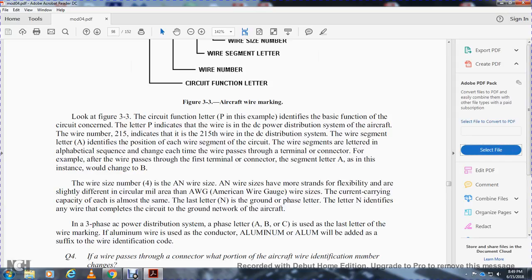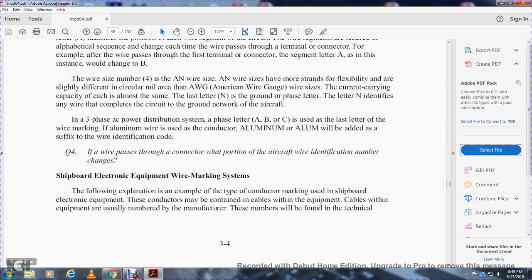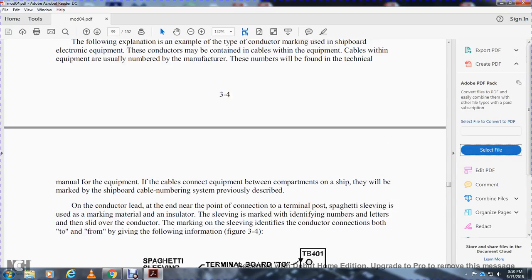In a three-phase AC power distribution system, the phase letters A, B, and C are the last letter of the wire marking. Aluminum wire conductors use the suffix 'AL' to the wire identification code. Shipboard electronic equipment wire marking system: conductors used in shipboard electronic equipment may be contained in cables within the equipment; those cables are usually numbered by the manufacturer and found in the technical manual. If cables connect equipment between ship compartments, they are marked using the shipboard cable numbering system. For conductor leads near terminal post connections, spaghetti sleeving is used as the marking material — the sleeving is marked with identifying numbers and letters and slid over the conductor.